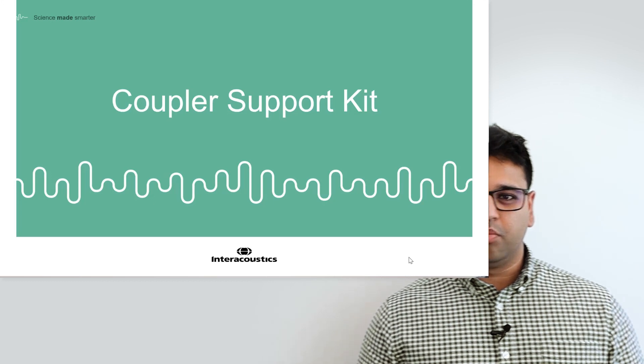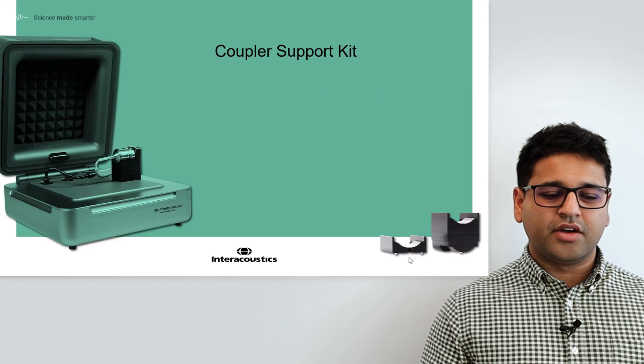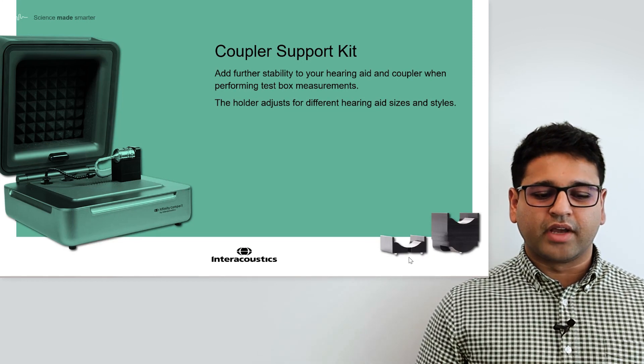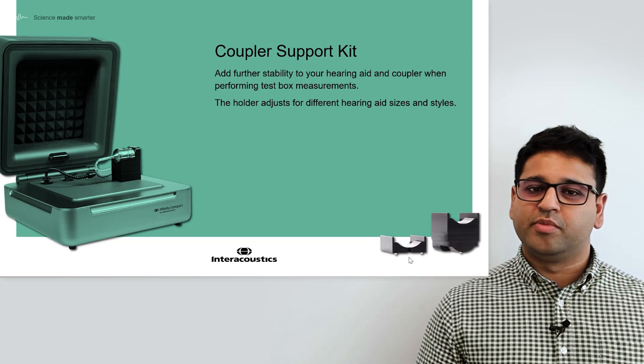Secondly, I'd like to move on to the Coupler Support. This is something that will help you to connect your hearing aid but provide further stability to your hearing aid and Coupler when you're performing test box measurements — whether for HIT testing, RECDs, or Coupler fitting of hearing aids.